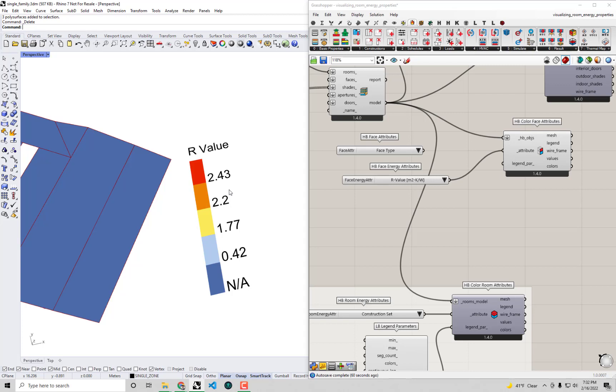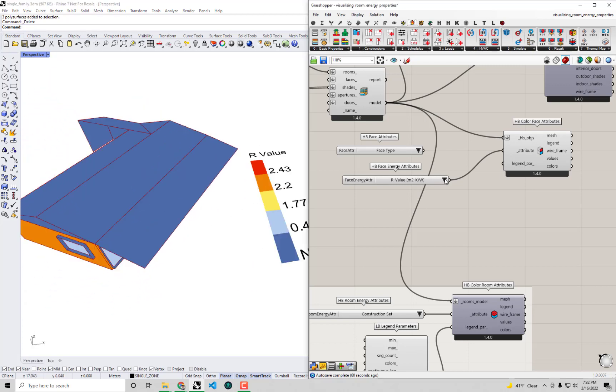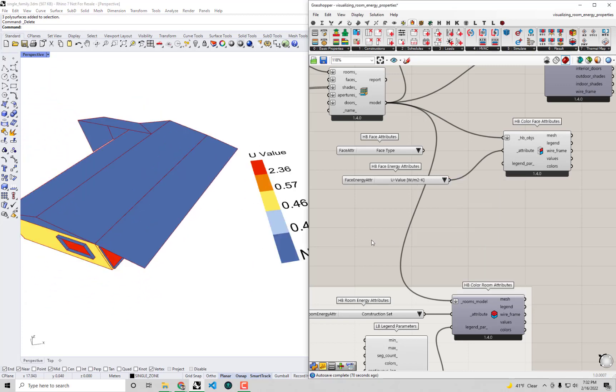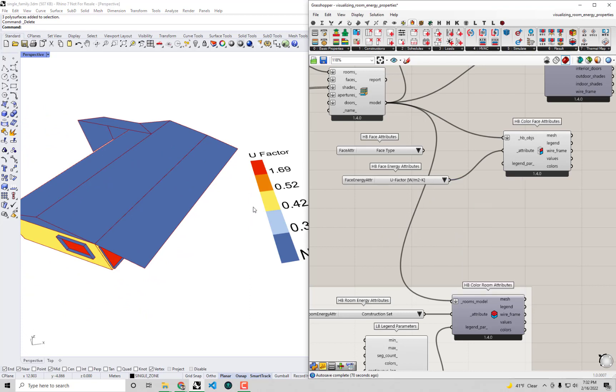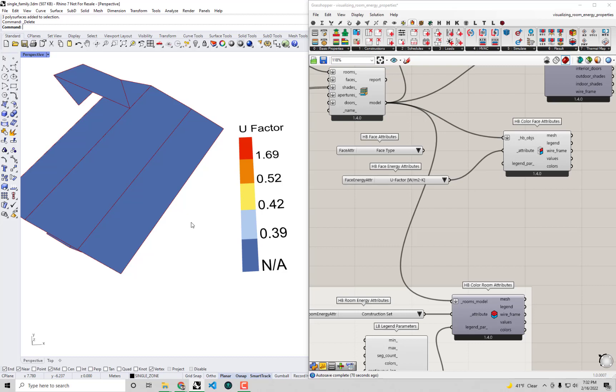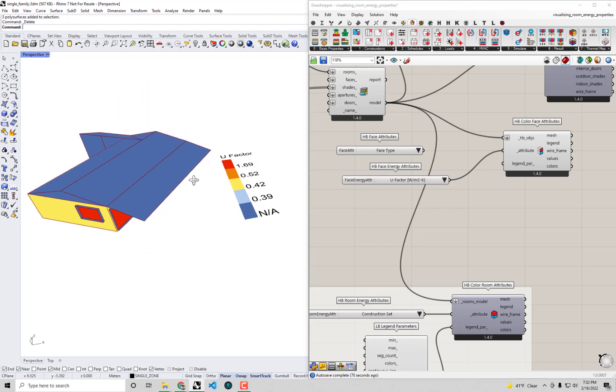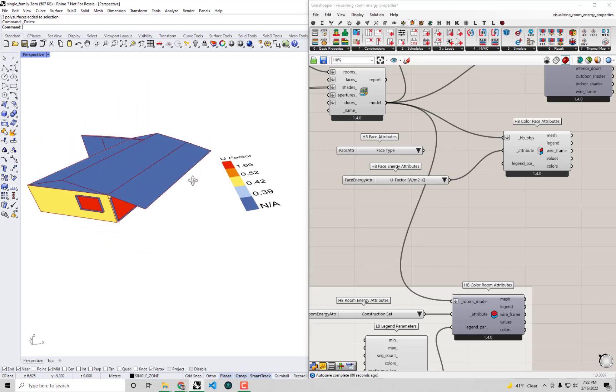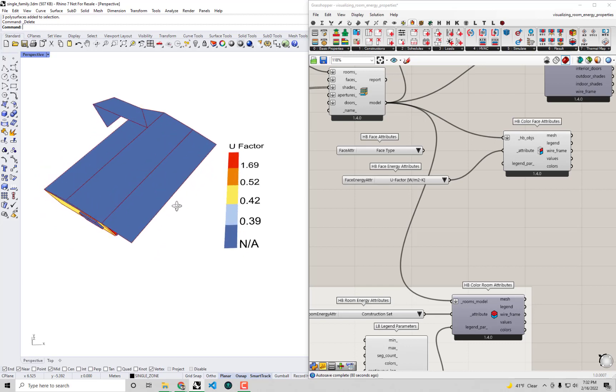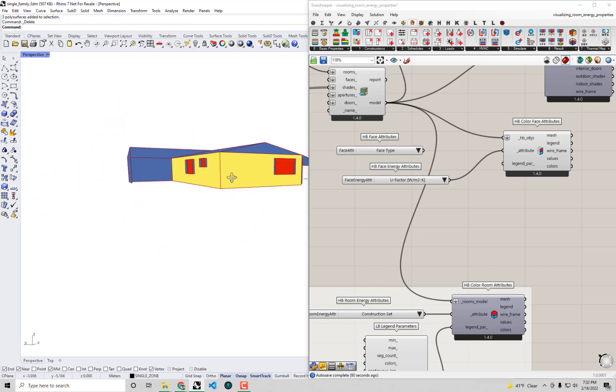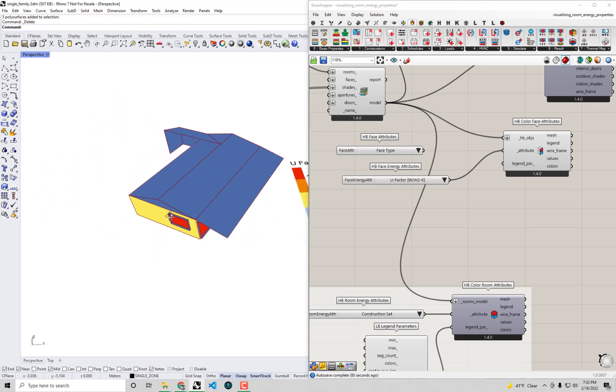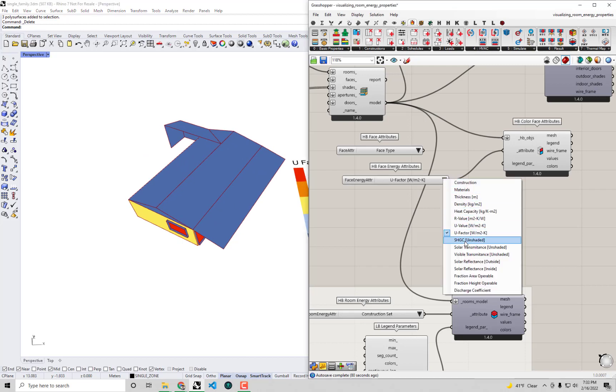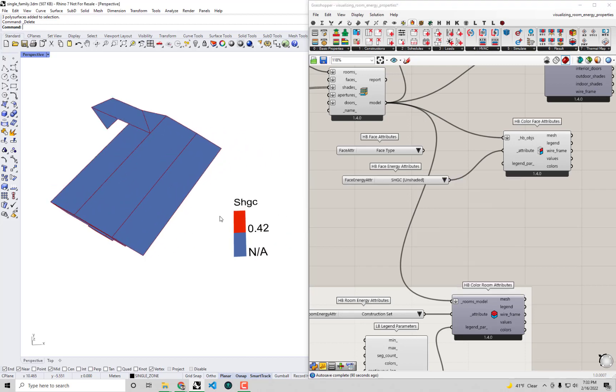What else do we have here? We can check the U value of the windows or probably more specifically we might want to know the U factor which is going to account for things like the air film resistance. We can see our windows have a U factor of 1.69 in metric which is pretty standard double pane with a low E coating. We can check things like the SHGC, the solar heat gain coefficient.